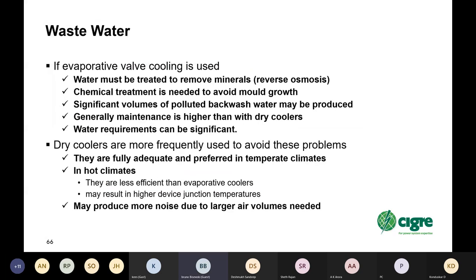Wastewater, we won't spend any time on. Water needs to be treated to remove minerals. Chemical treatment is needed to avoid mold growth. A significant volume of polluted backwash water may be produced. Maintenance is higher than with dry coolers. Dry coolers are the most frequently used coolers. They're fully adequate and preferred in temperate climates. They may not be completely effective in very hot climates, and therefore evaporative cooling may still find some use.